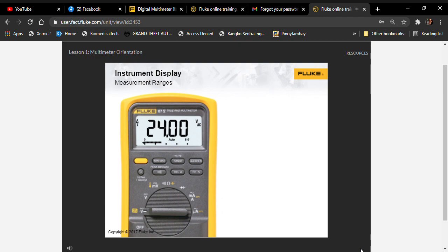If you were to measure a very different voltage level, such as a 24 volt control circuit, the multimeter would automatically switch to a different range. In this case, the 0 to 60 volt range, and the display shows 24.00 volts. So, how does the multimeter choose the best range? It's the best range that provides the best resolution and still includes the measurement.